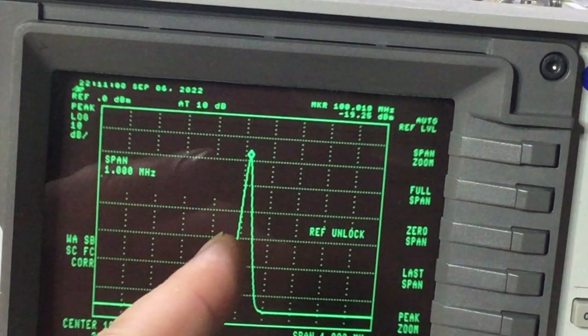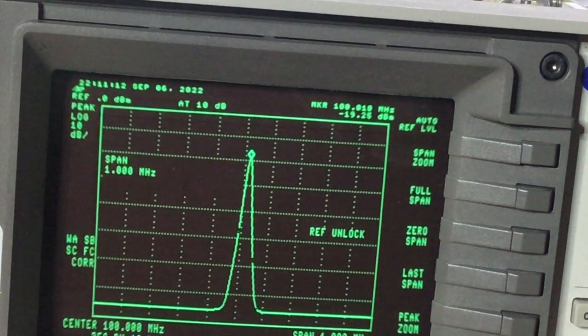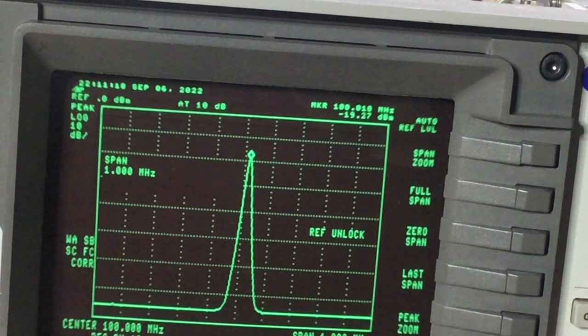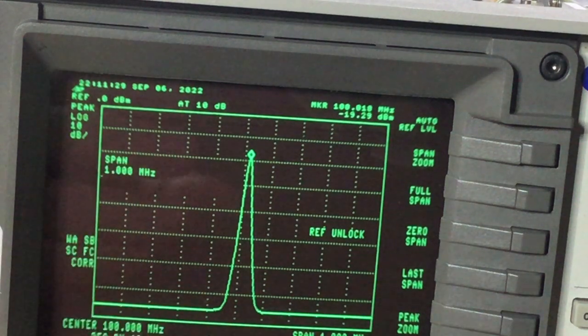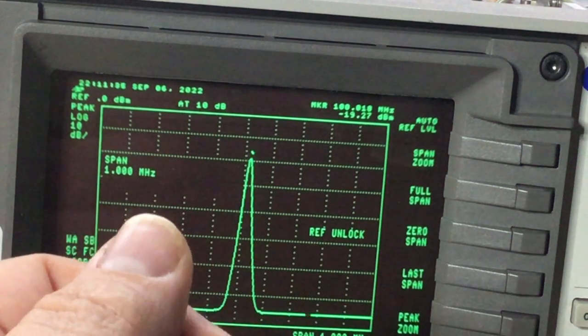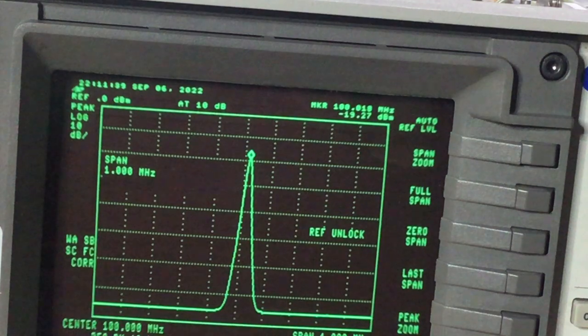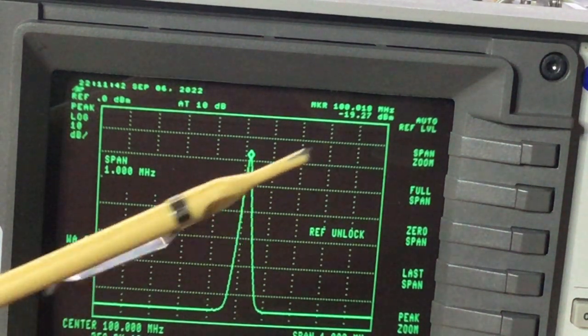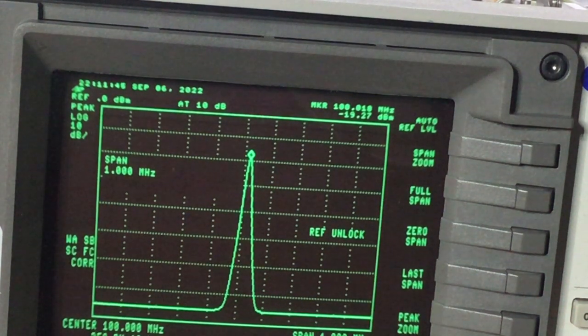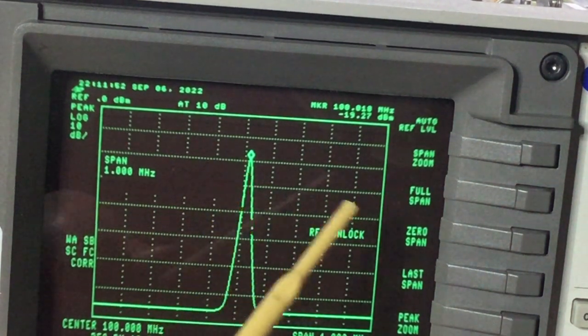Now if you remember earlier when we first started the video, the frequency was way off, and I think it could potentially be that the 10 meg oscillator was physically so far off frequency that it couldn't capture the frequency. I'm clutching at straws here when I say this, because it's more or less behaving itself now, but the only thing that we've done really is to manually tune the 10 megahertz oscillator, tuning the trimmer capacitor using, if you recall earlier, this trimming tool. In doing so, that seems to have made a major improvement in the frequency accuracy of the instrument, insofar as it not drifting way off frequency.